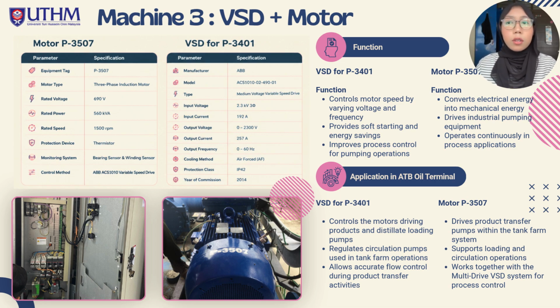Not all motors in ATB use VSD because VSDs are typically installed on pumps requiring speed and flow control. The VSD controls motor speed by varying output voltage and frequency. It enables soft starting and soft stopping, reduces mechanical stress and improves energy efficiency. The motor converts electrical energy into mechanical rotational energy to drive industrial pumps.